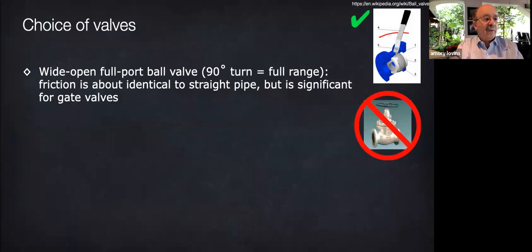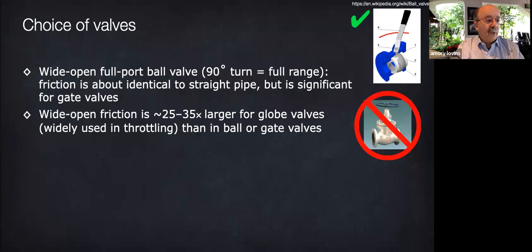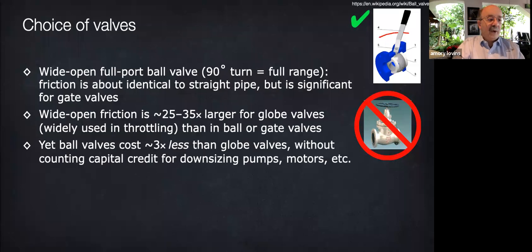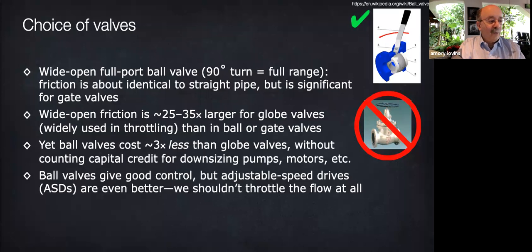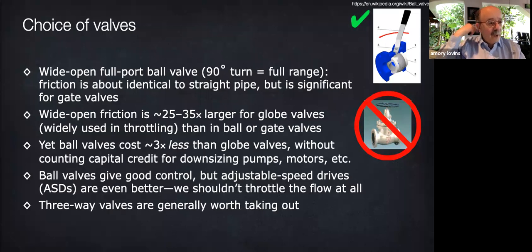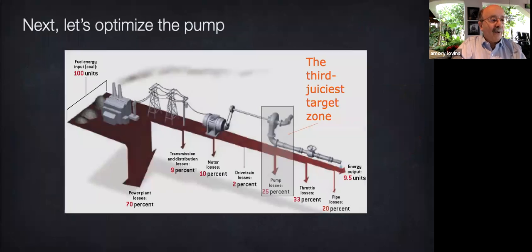For a lot of uses, I like full port ball valves, which have essentially no friction when wide open. It's just like a straight pipe. But gate valves have significant friction, and globe valves are awful in their friction. And yet they cost more than the ball valves. And I'm not even counting capital credit for shrinking the pumps and motors and so on. Ball valves do give good control, but adjustable speed drives are even better. They give exact control, and we shouldn't throttle the flow at all. And then there are these things called three-way valves that are generally worth taking out.